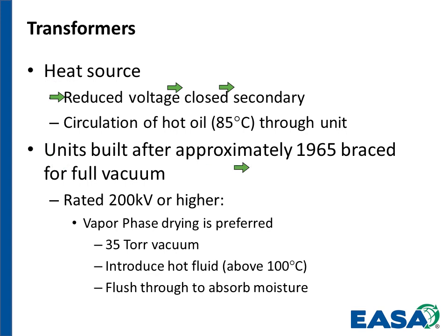Transformers built after approximately 1965, as part of their construction, were braced for full vacuum. So that means that with that type of transformer of that vintage, you can drain the oil, filter it separately, pull a full vacuum, and evacuate the moisture. So vapor phase drying is preferred. If you can hit about 35 microns with a vacuum, introduce hot fluid, hot oil, and flush that through to absorb the moisture, then you're usually able to clean the transformer and dry it pretty effectively and remove the oil.